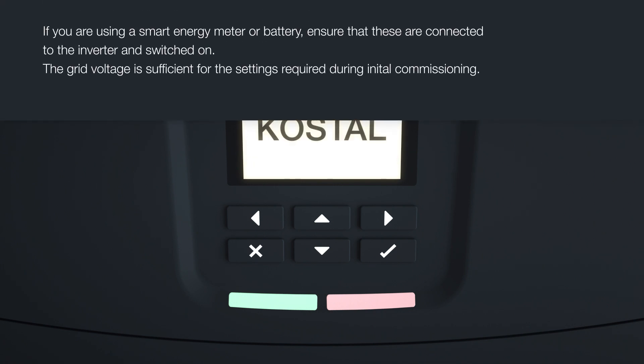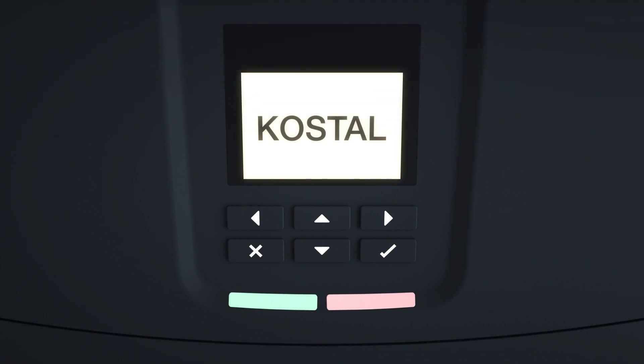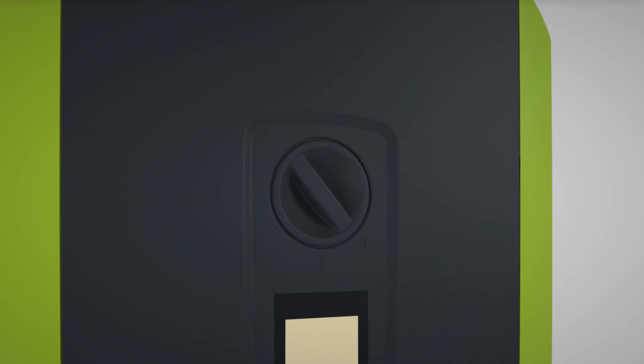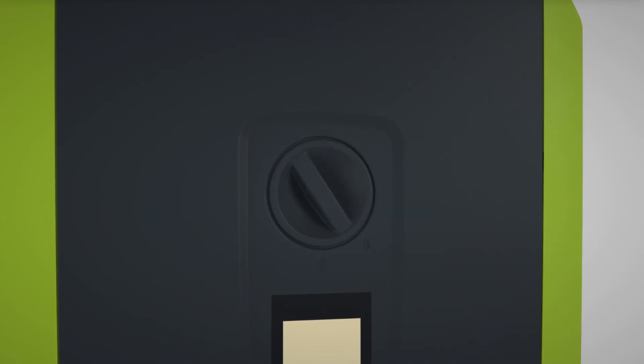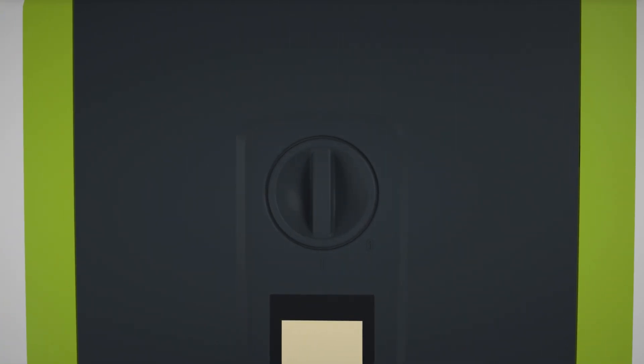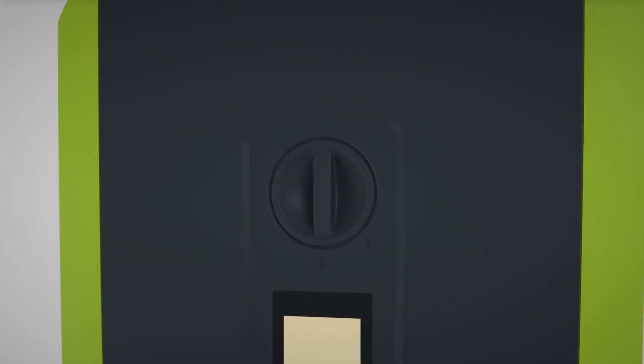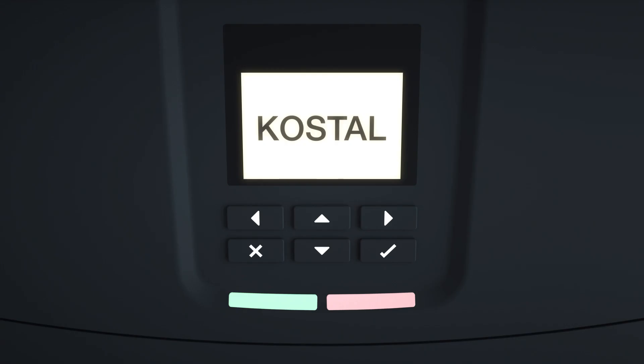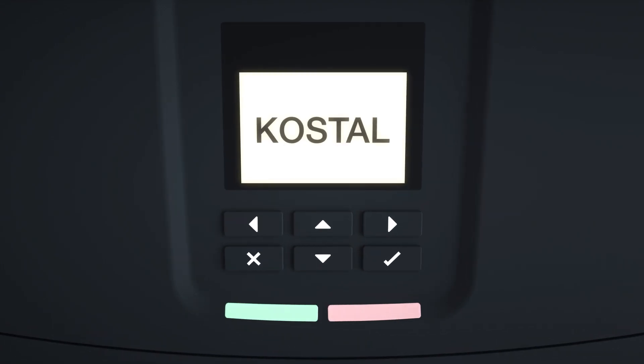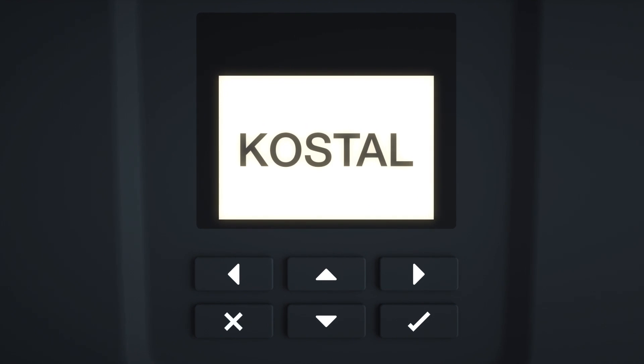First, switch on the grid voltage via the line circuit breaker. The device software launches. Turn the DC switch to the ON position. The entire commissioning process can be undertaken via the display.